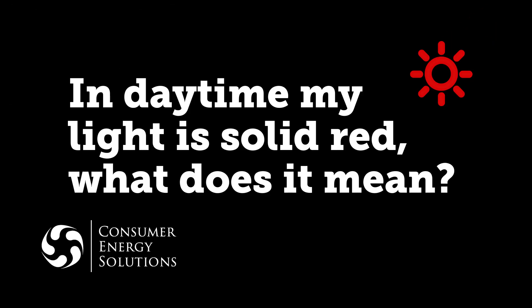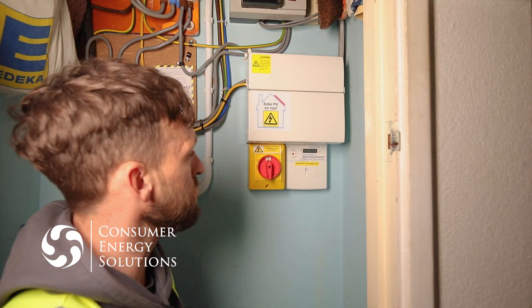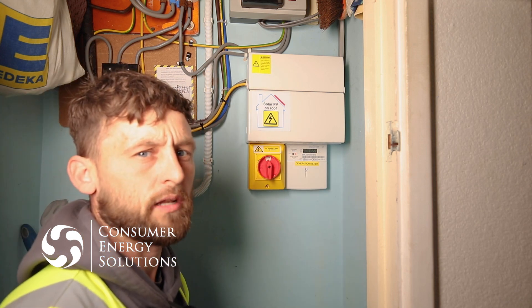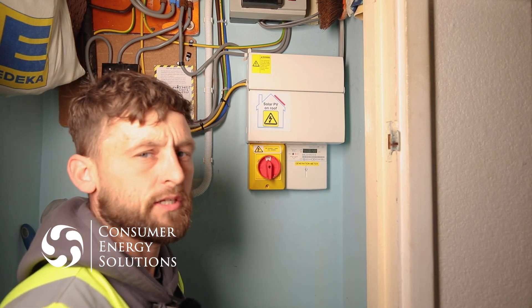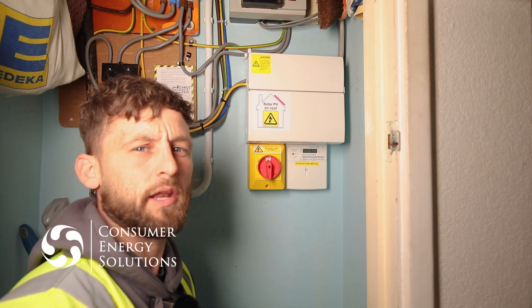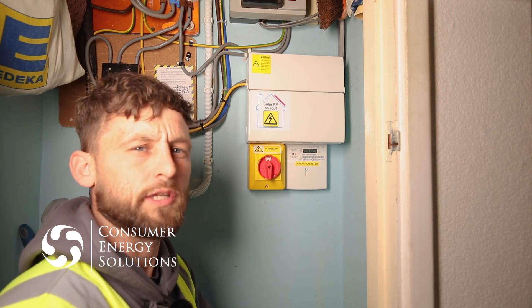It's important to check your generation meter regularly. What I'd like to do is show you where to find it, what it looks like, and how to identify any potential problems. When checking our generation meter, if you identify that it is a solid red light, this is the first stage of identifying there could potentially be an issue with your solar installation.